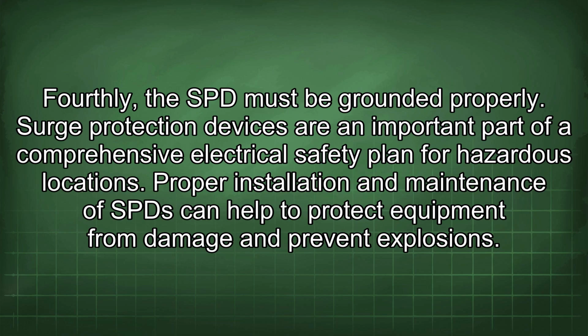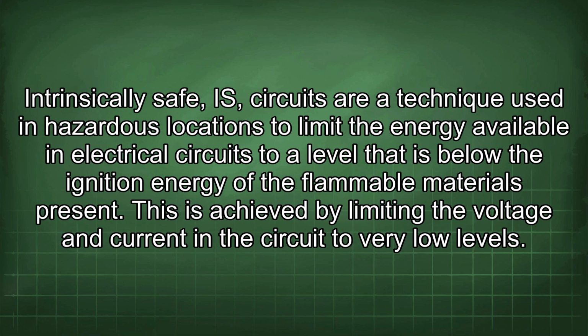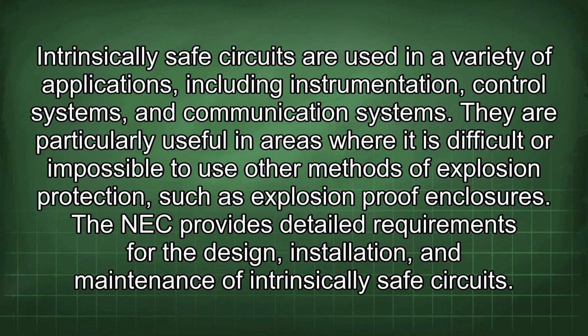Surge protection devices are an important part of a comprehensive electrical safety plan for hazardous locations. Proper installation and maintenance of SPDs can help to protect equipment from damage and prevent explosions. Intrinsically safe circuits are a technique used in hazardous locations to limit the energy available in electrical circuits to a level that is below the ignition energy of the flammable materials present. This is achieved by limiting the voltage and current in the circuit to very low levels. Intrinsically safe circuits are used in a variety of applications, including instrumentation, control systems, and communication systems. They are particularly useful in areas where it is difficult or impossible to use other methods of explosion protection, such as explosion-proof enclosures. The NEC provides detailed requirements for the design, installation, and maintenance of intrinsically safe circuits.